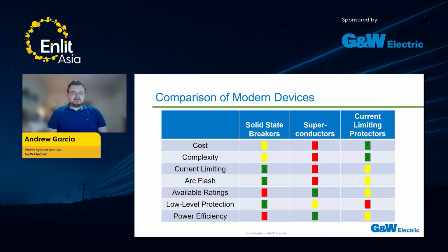In terms of complexity, once again, current limiting protectors take the cake. They're a very simple device to install, with a very simple principle of operation that's very easy to understand, and a simple-to-understand electronic triggering scheme. Solid state breakers come in second. Once you have trained on those devices, they're pretty easy to understand. Basically, all you need to understand is that when you set it, that breaker's going to clear that fault in microseconds. Superconductors are the most complex because it's a new type of cable that needs to be laid a long distance. You also need to be able to set up those cryogenics and handle them in a safe manner, so you're going to have to train a lot of your personnel.